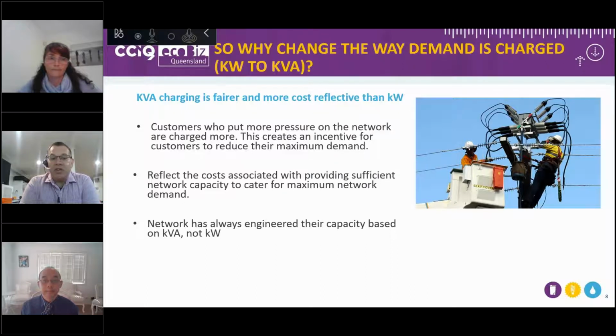kVA also reflects the cost associated with providing sufficient network capacity to cater for the demand. The reason is that the network is built based on kVA, not kilowatts. So we build and engineer our capacities, and we use figures based on the kVA capacity, not the kilowatt capacity.